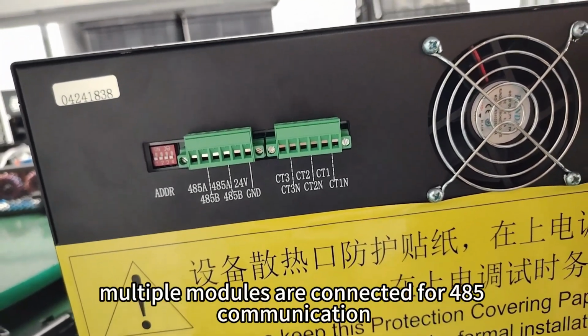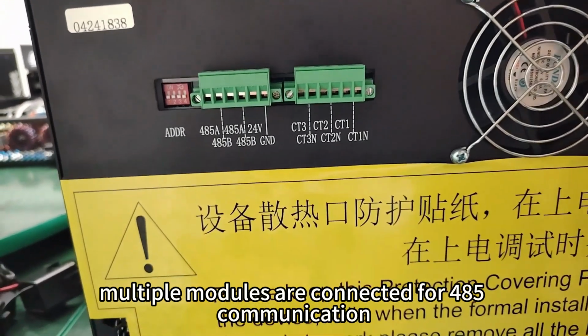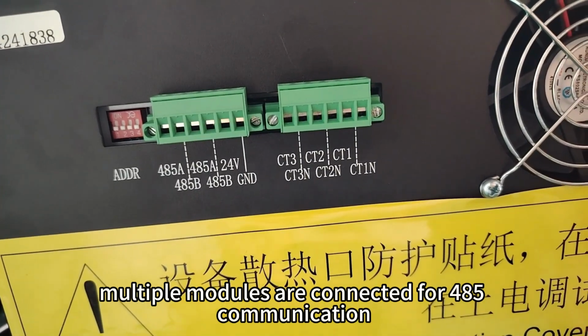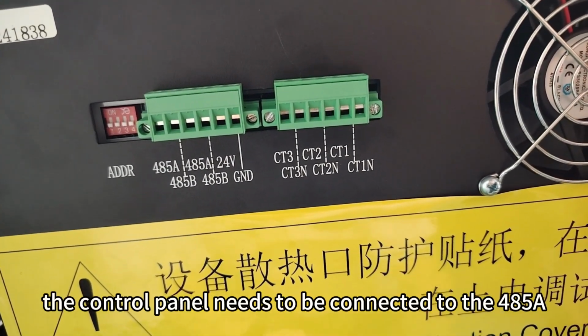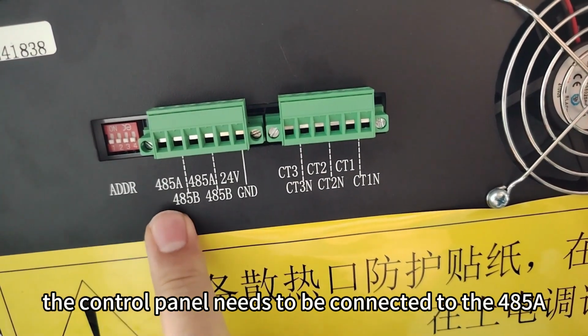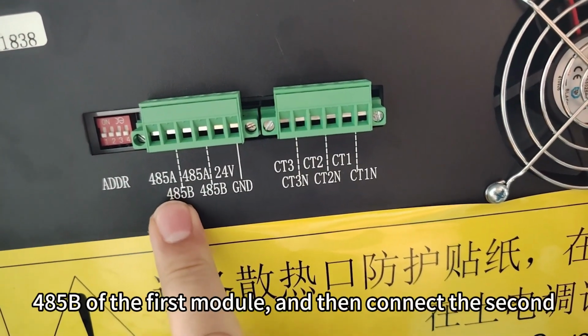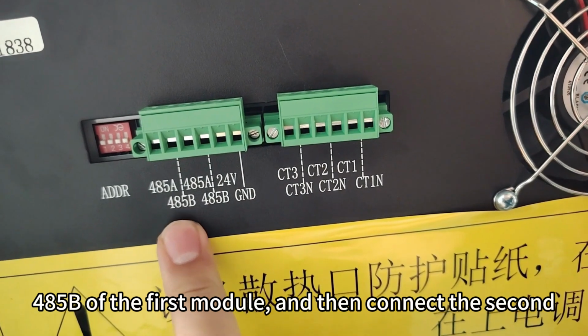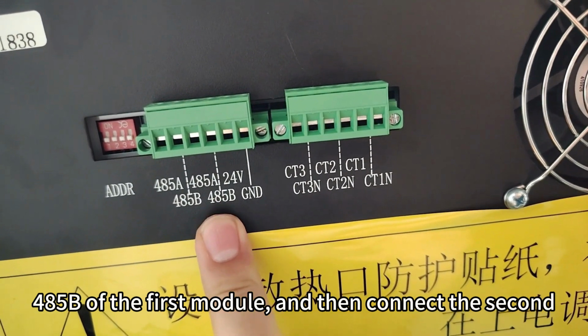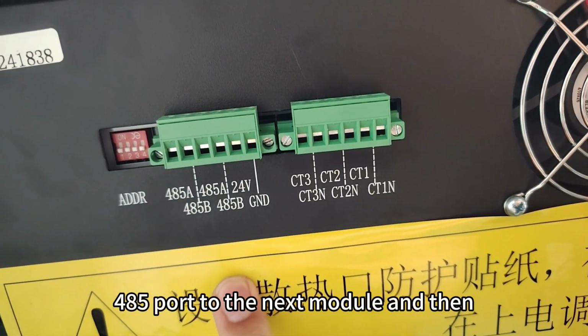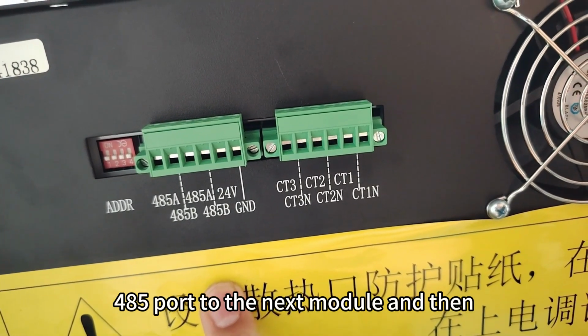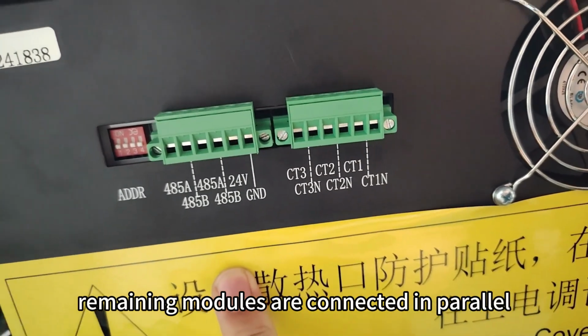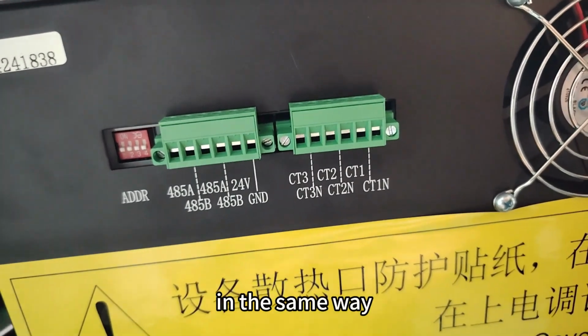Okay, when multiple modules are connected for 485 communication, the control panel needs to be connected to the 485A, 485B of the first module, and then connect the second 485 port to the next module, and the remaining modules are connected in parallel in the same way.